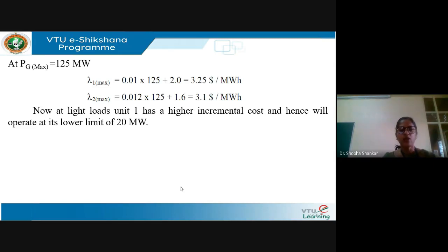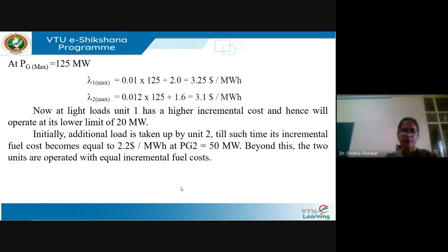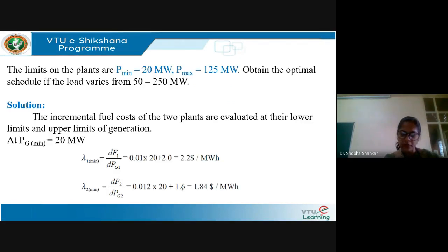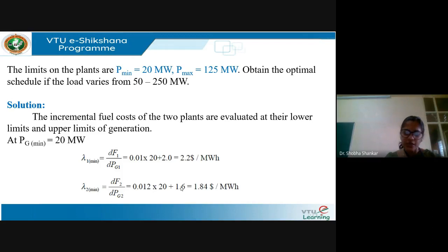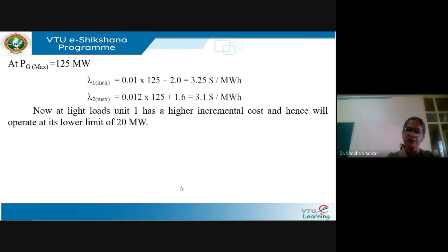At light loads, unit one has a higher incremental cost and hence needs to be operated at its lower limit only, because the cost of generating higher output would be more for plant one than plant two. Therefore, the additional load is initially taken up by the second unit until its incremental fuel cost becomes equal to 2.2 $/MWh, which corresponds to PG2 = 50 MW.